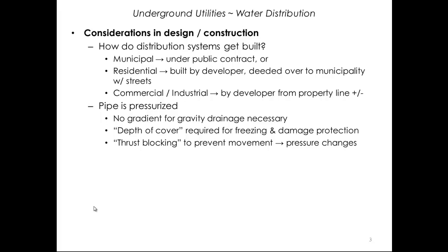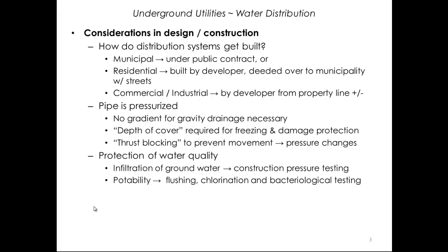The other issue is that water lines can be subject to some movement as consumption cycles on and off. This movement has the potential over time to cause leaks on the lines. To prevent this, the use of concrete blocking is required at all bends, fittings, and hydrants. Another consideration is the quality aspect of the water. Potable water, by definition, is drinking water quality.